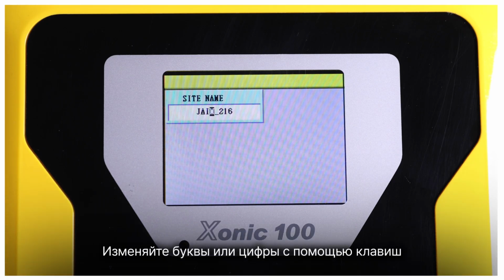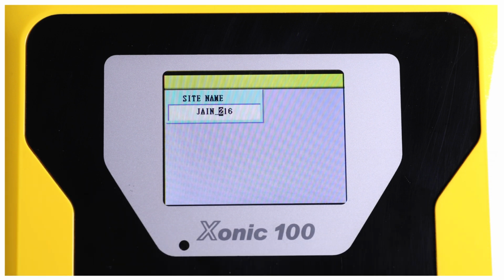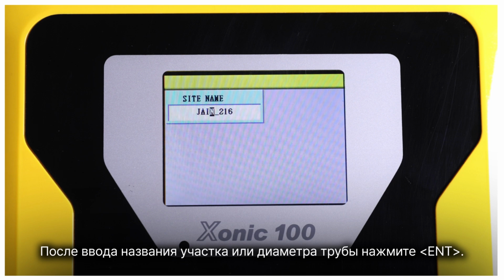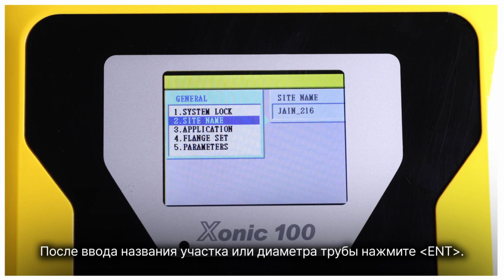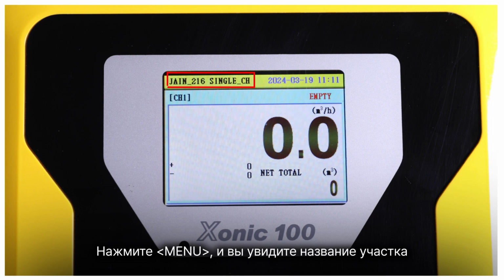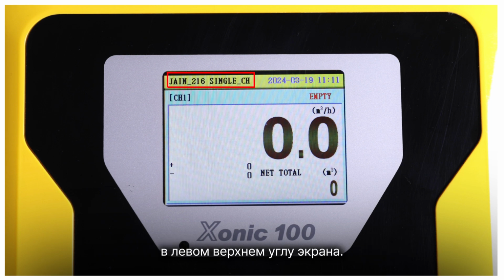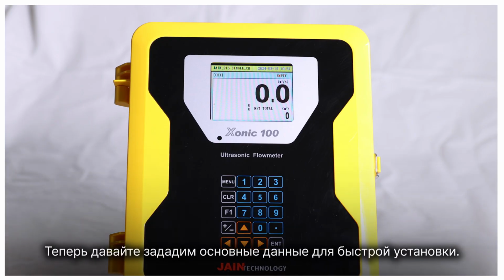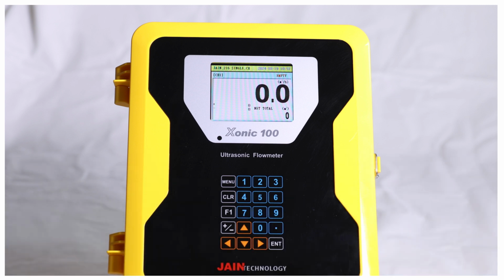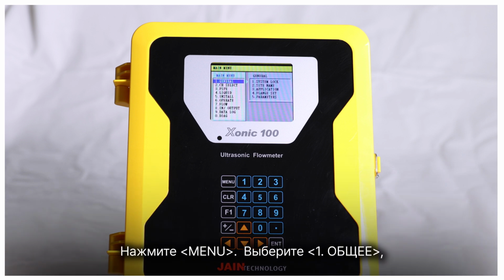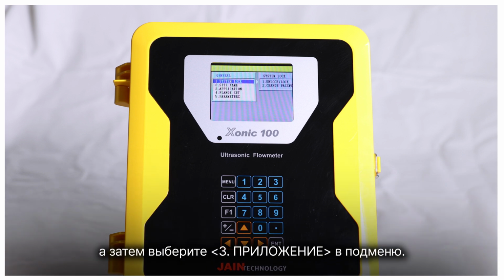Change letters or numbers with the up and down arrow and number keys. After typing the site name or pipe diameter, press Enter. Press Menu and you will see the site name on the top left corner of the screen. Now let's set up the basic data for a quick installation. Press Menu, select 1, General, and then select 3, Application on the submenu.